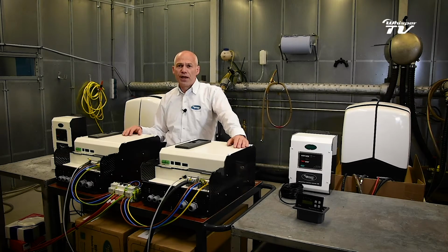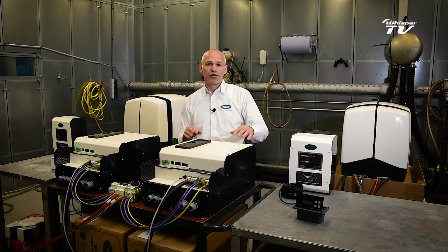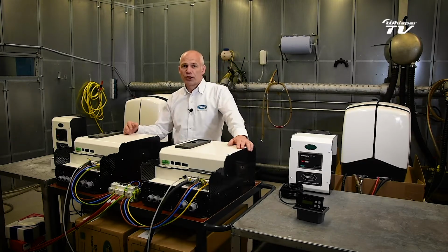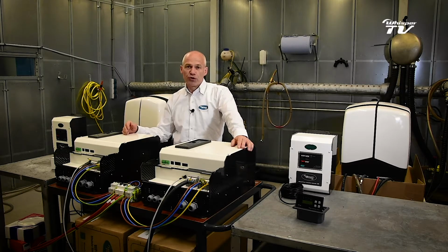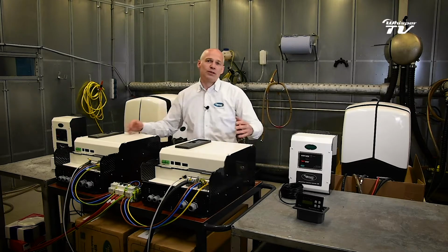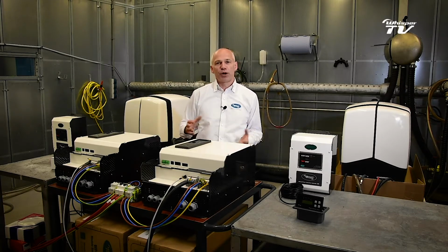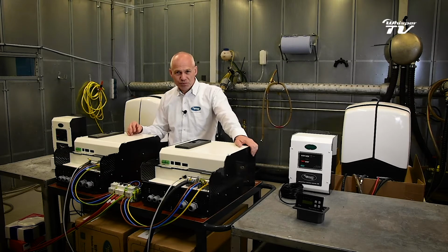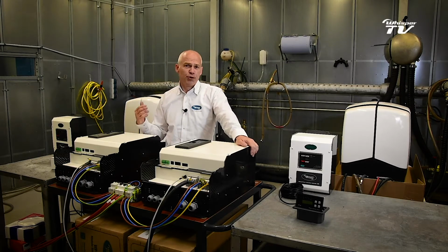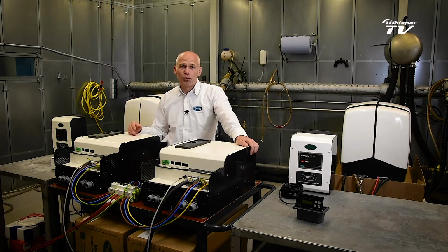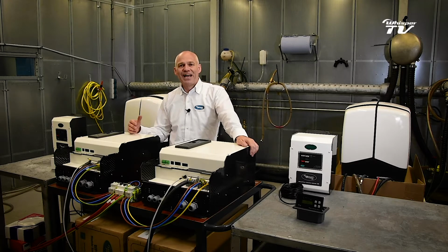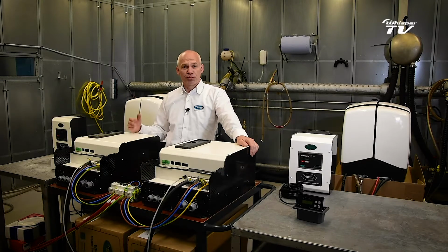Then the redundancy. In case of a technical failure with one of the units, the other unit can take over the power supply to your system. So there is always one spare power source available. Well, the all water-cooled design principle allows stowing the generator in places where we have limited air circulation. And the system is fully compliant with stage 5. The engines are running cleaner with less fuel consumption, and the engines are also compliant with Tier 4 EPA, and they approved it as well.